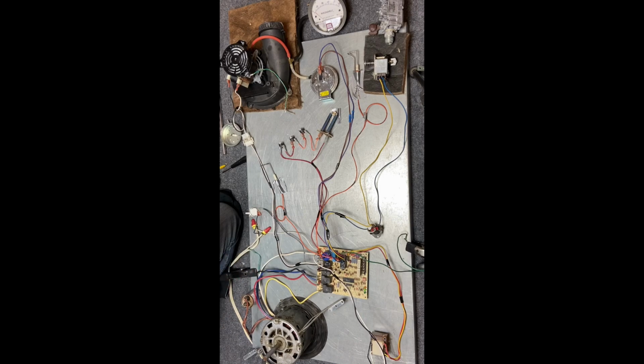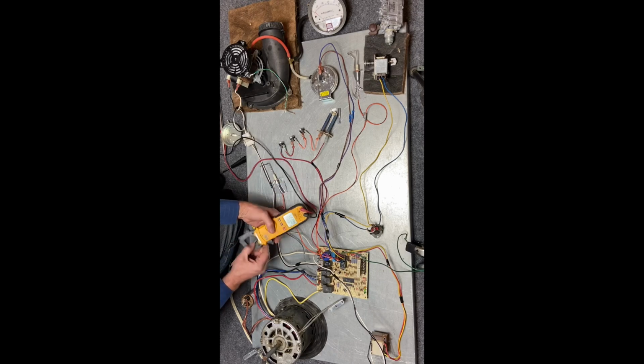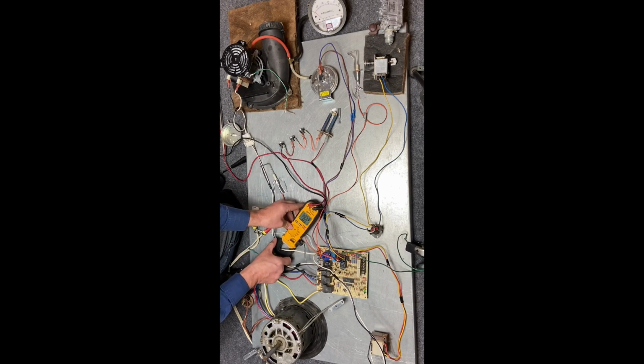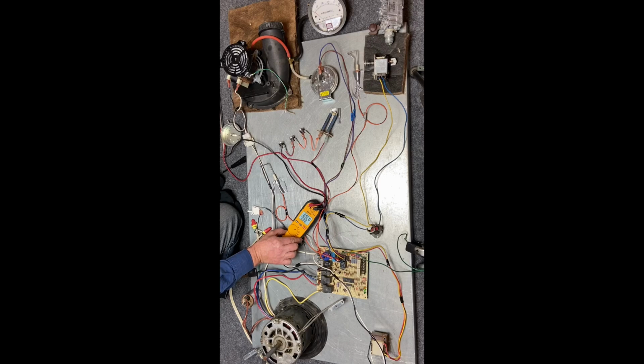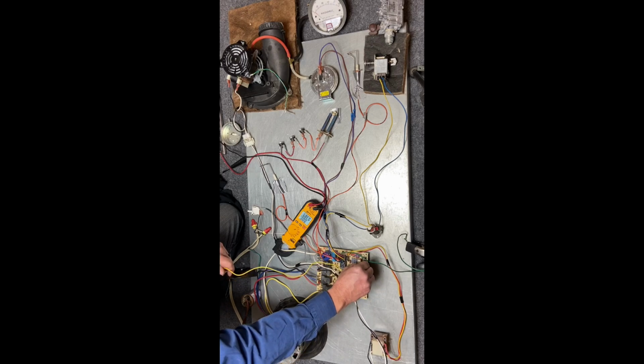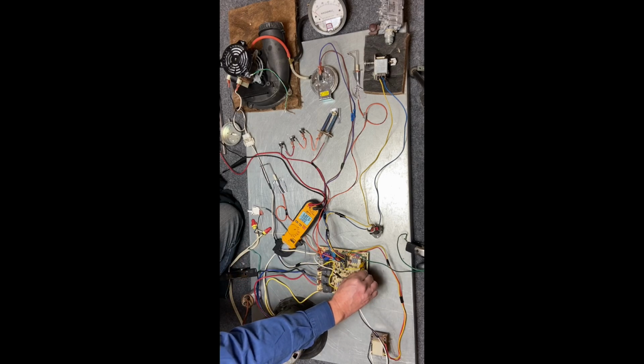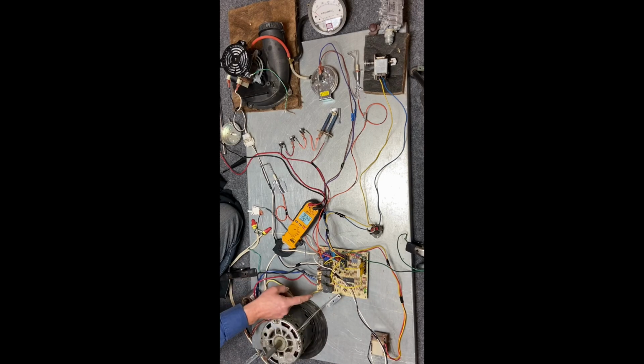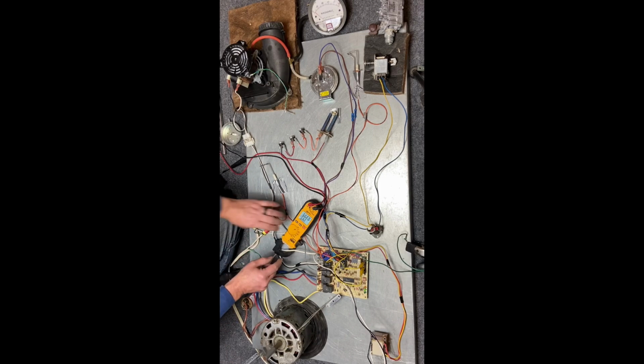So what we're going to do is have a call for fan. So when a thermostat calls for fan, it's going to connect R to G. G stands for indoor fan relay. So I'm going to do that very thing. But what I'm going to do is clamp around this common wire. And if you look at this very top number here, let's see if I can turn the light on. And we're going to jumper this so the fan will come on. You'll start seeing a flow of amperage. So we're going to connect from R to G. And what that should do is energize, for fan, this relay is going to energize this speed. And we can see we're pulling 1.49 amps through the common side.